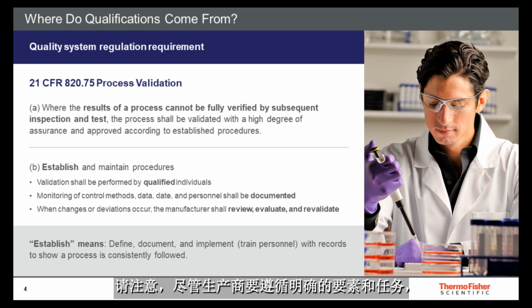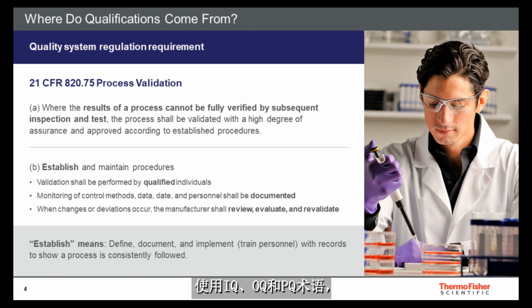Note that despite having explicit elements and tasks for manufacturers to follow, it does not call out the qualification mechanism. So where do qualifications come from? It is in the FDA Medical Device Quality Systems Guidance document from 1996 that first officially established the use of IQ, OQ, and PQ terminology for medical devices, separate from the previous medical device GMP regulation.